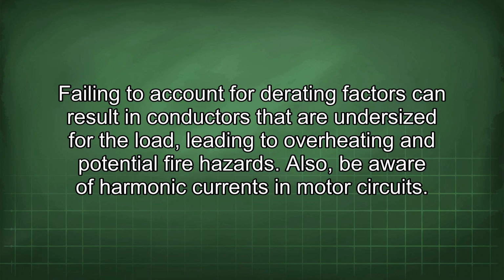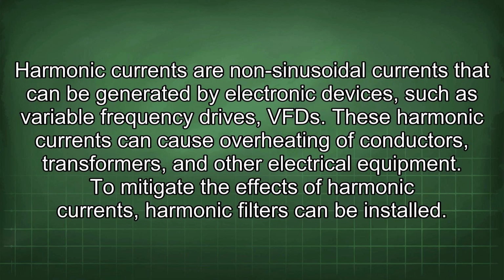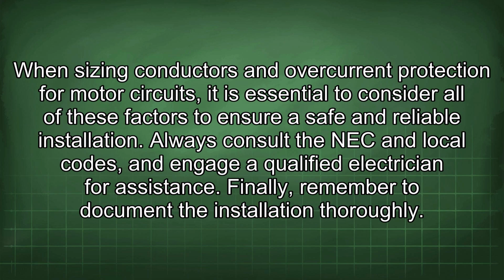Also, be aware of harmonic currents in motor circuits. Harmonic currents are non-sinusoidal currents that can be generated by electronic devices such as variable frequency drives, VFDs. These harmonic currents can cause overheating of conductors, transformers, and other electrical equipment. To mitigate the effects of harmonic currents, harmonic filters can be installed. When sizing conductors and overcurrent protection for motor circuits, it is essential to consider all of these factors to ensure a safe and reliable installation.